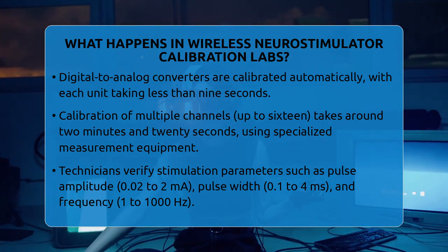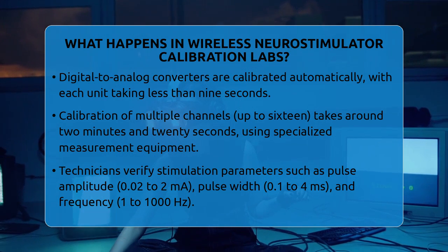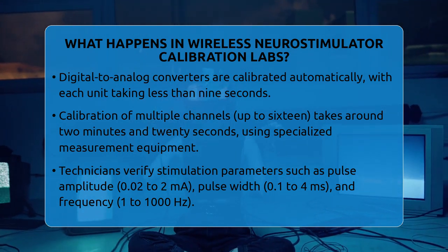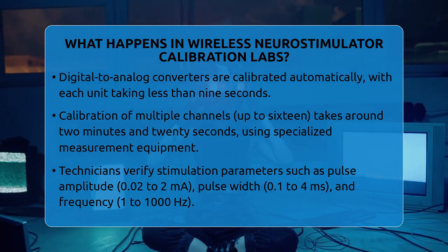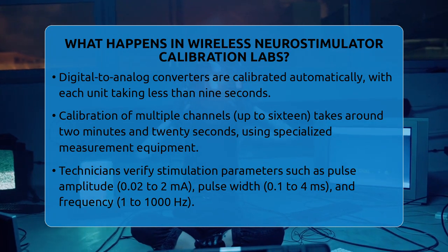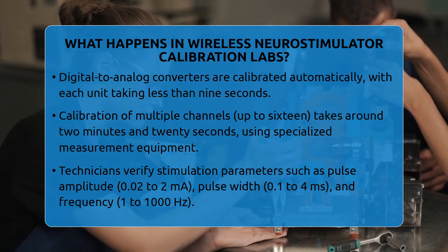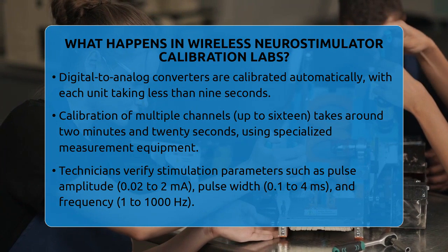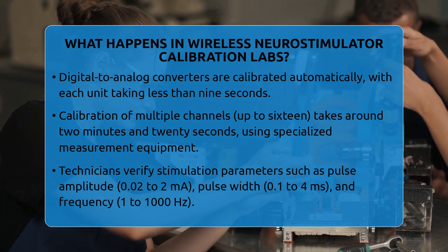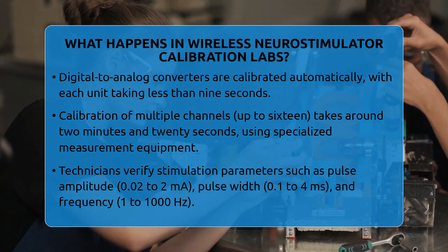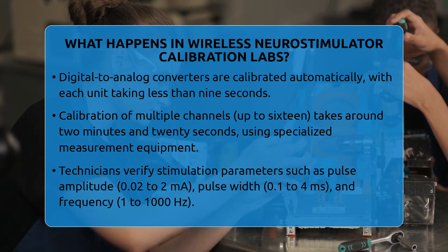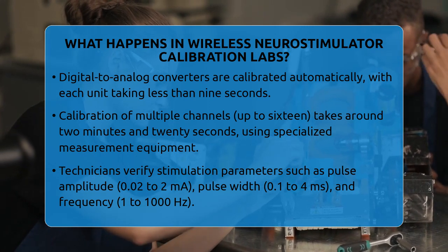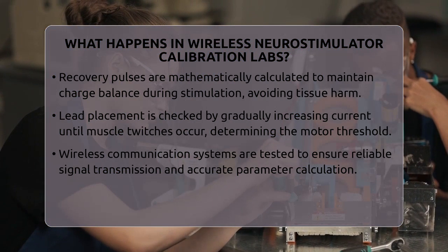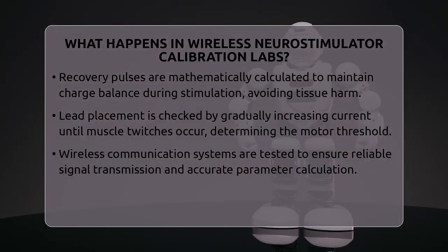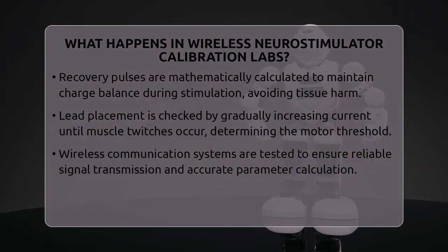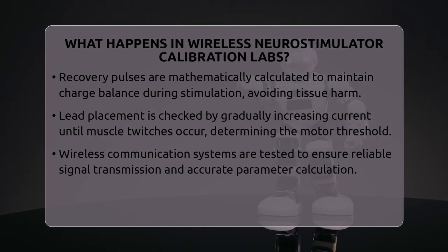Technicians then verify the stimulation parameters. They check that pulse amplitudes stay within the set range, usually from 0.02 to 2 milliamps. Pulse widths are tested between 0.1 and 4 milliseconds, with increments of 0.1 milliseconds. Frequency settings are verified across 1 to 1000 Hz. Recovery pulses are calculated mathematically to keep charge balanced during stimulation. This ensures no excess charge builds up, which could harm tissue.